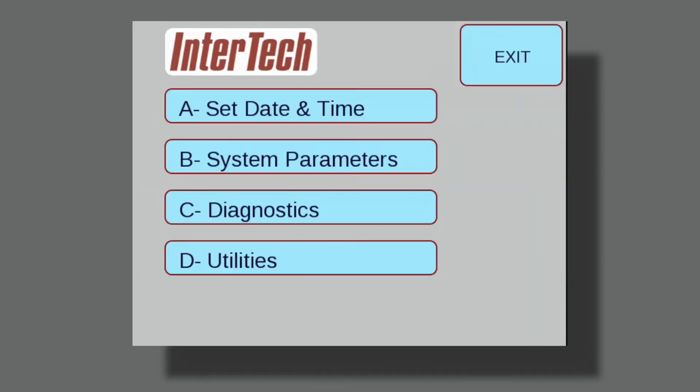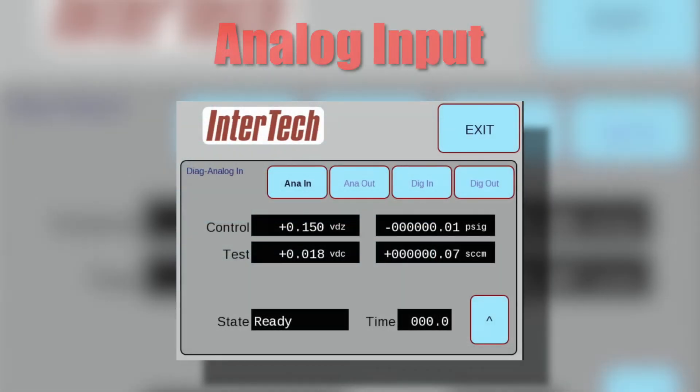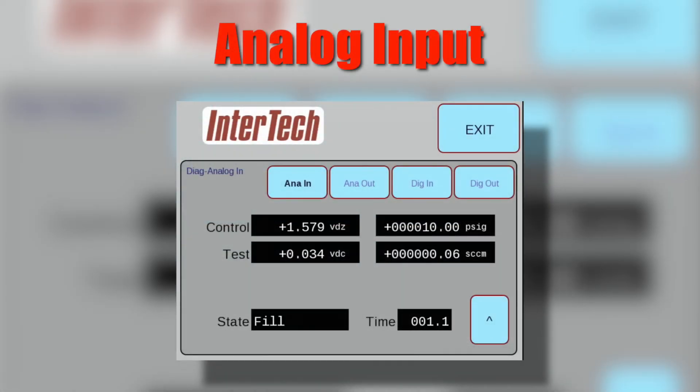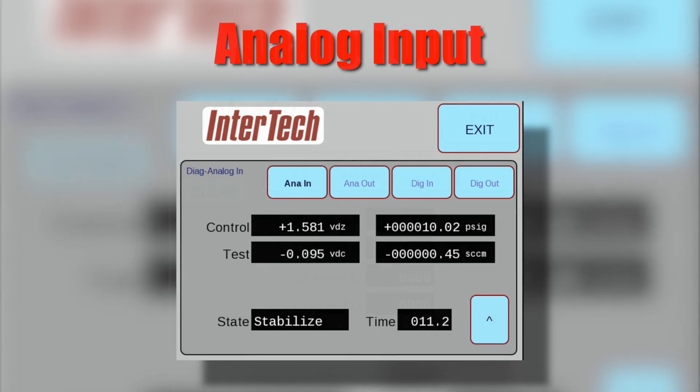Additionally, in the supervisor mode, diagnostics can be selected including digital and analog inputs and outputs functions. The analog input display allows the operator to cycle through the tester operating modes and see unfiltered real-time display of pressure sensor and mass flow sensor voltage input and their output values.